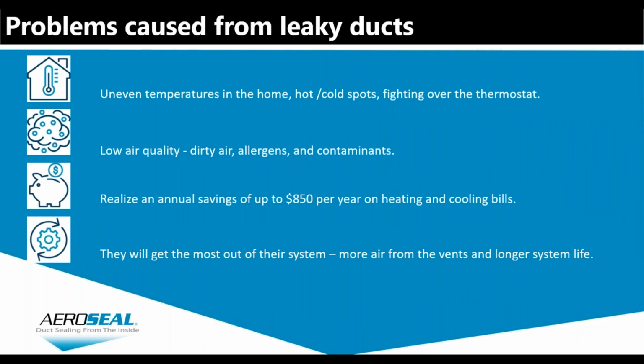So let's jump to the next slide. There are a lot of problems caused by leaky ducts, several listed here. The top one is uneven temperatures in the home, hot and cold spots, and fighting over the thermostats. That fighting may or may not be exaggerated depending on the condition of the home, but homeowners do have rooms or areas that heat and cool differently depending on how much air loss occurs along the way. According to the Department of Energy, it's typical that 10 to 40% of the conditioned air is leaking out of the ductwork on its way to the register. On a 3-ton air conditioner system, that's a loss of about 1 ton of cooling capacity.